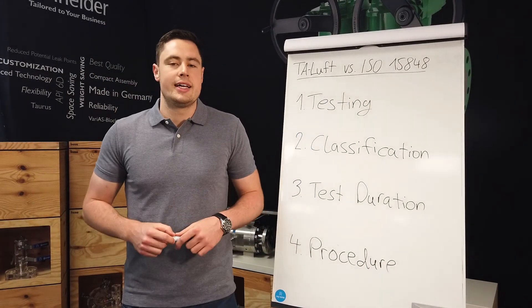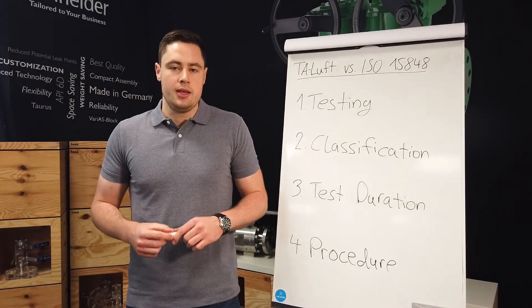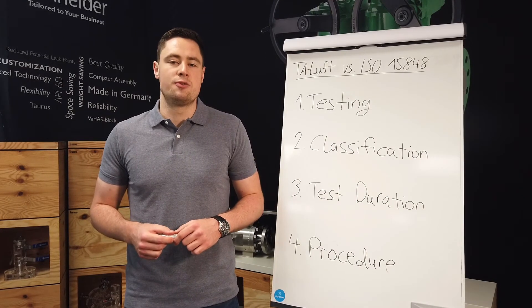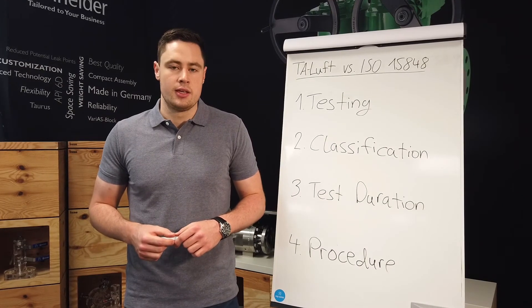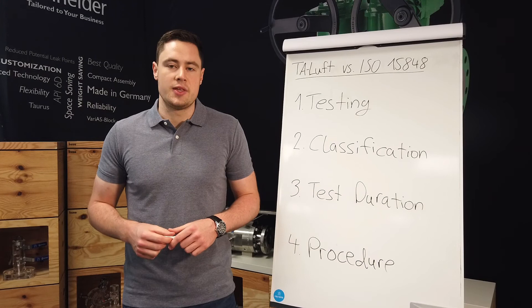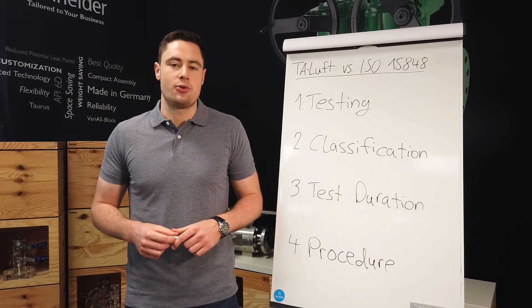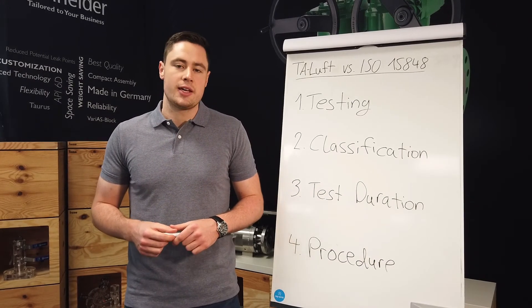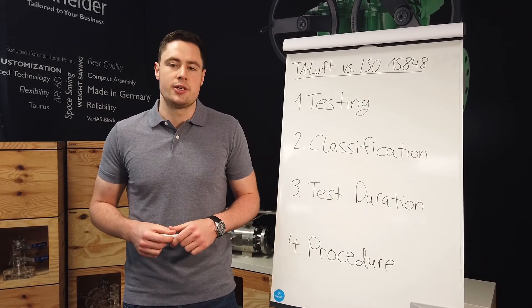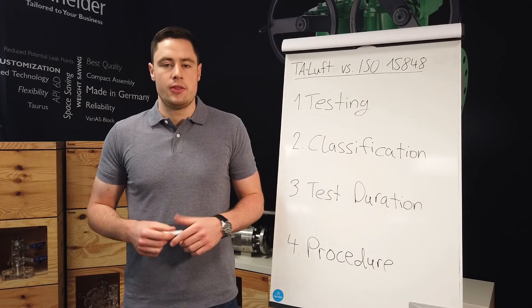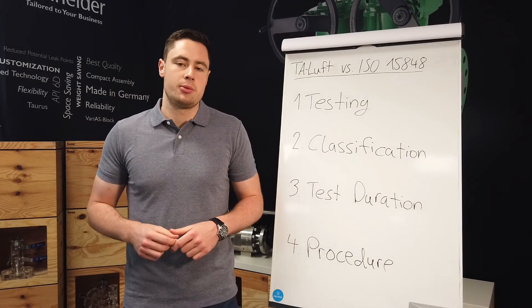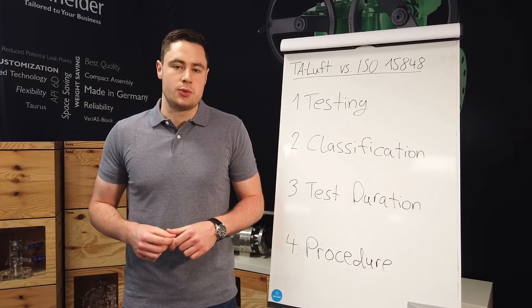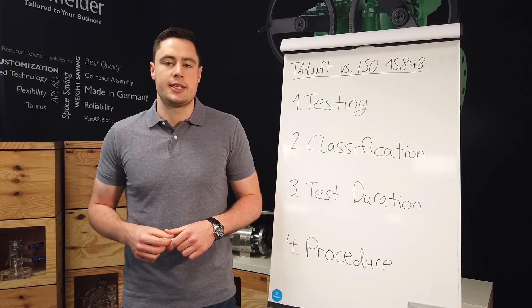Let's have a look at TA Luft. Many seal manufacturers like to advertise with TA Luft packings. Simply using TA Luft packings of this type does not guarantee long-term leak tightness — many other factors play a significant role in a sealing system. These include, for example, the stem surface finish and the gap dimensions between the gland and the stem.